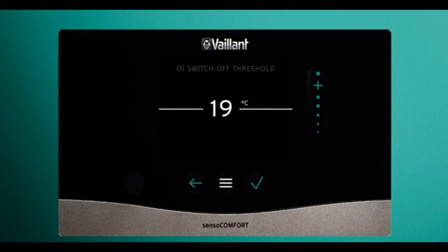Next is the switch off threshold. This is a temperature at which, when the outside reaches that set value, it will switch to heating off and not produce any heat for the heating system until it drops below this value. So once it drops below 19°C it will resume heating, and when it gets to 19°C and above it will stop. This does not affect hot water production at all.